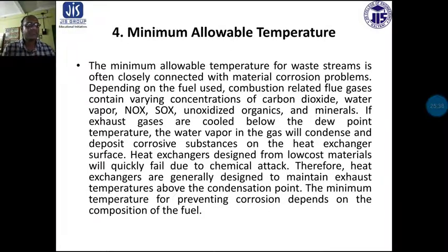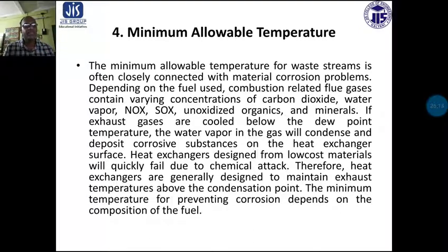Minimum exhaust temperature may also be constrained by process-related chemicals. For example, sulfates in exhaust gases from glass melting furnaces deposit on heat exchanger surfaces at temperatures below 270°C. The most common prevention method is designing heat exchangers with exhaust temperature well above the dew point. Some systems use advanced alloys to further recover low temperature heat, but these have seen limited commercial application due to high material cost, large surface area requirements, and lack of available end uses for low temperature waste heat.